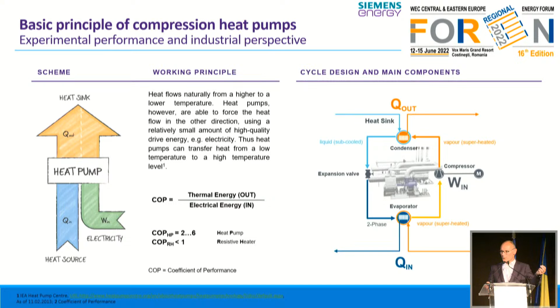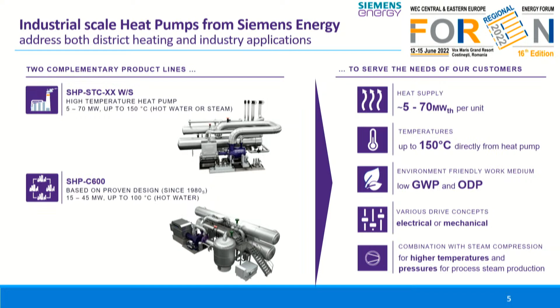At Siemens Energy we have, as I mentioned, two product types or product lines. One is the high temperature heat pump you see in the left top box. This is a heat pump which is right now more or less unique on the market, where we can produce temperatures up to roughly 150 Celsius as output temperature of the heat pump. You also see the power, as we are speaking really about industrial heat pumps. Our heat pumps are more for large scales, starting from 5 megawatt thermal output, going up to 70 megawatt thermal output with a single heat pump.